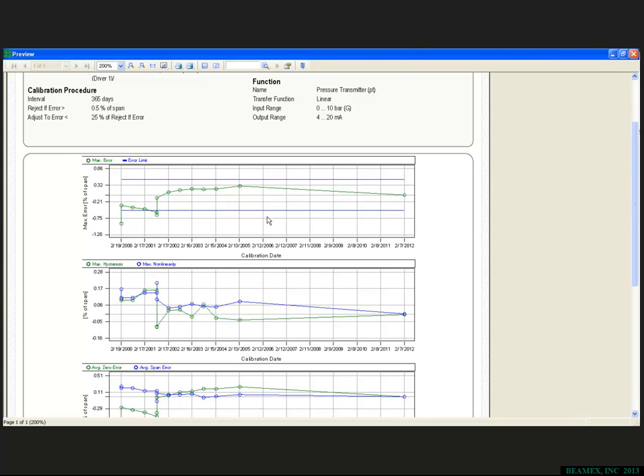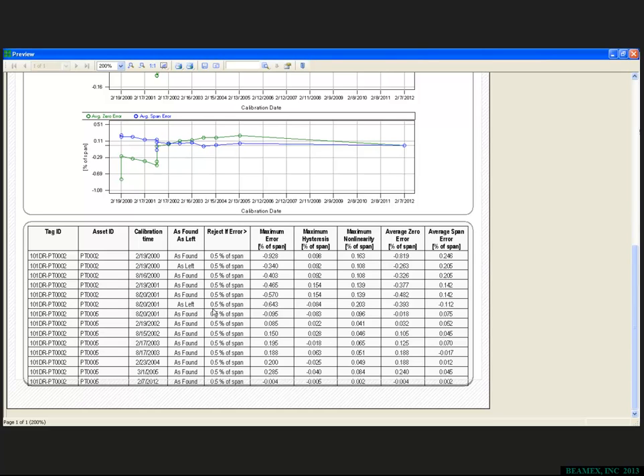And what we're looking at here is a graphical representation of each one of those calibration periods for this particular device. And then if we scroll down to the bottom, you can see all of the information in terms of the numerical values of this particular history trend. So you can actually see that the tag ID stayed the same. The asset ID changed, meaning that it was replaced at one point, here in August of 2001. It was replaced with a new asset, and at that time it was out of tolerance and deemed to be out of service. So a new asset was put in, and over time, the average span drift has been very minimal, which justified, back down here in 2004, adjusting the interval so that it was now 12 months.